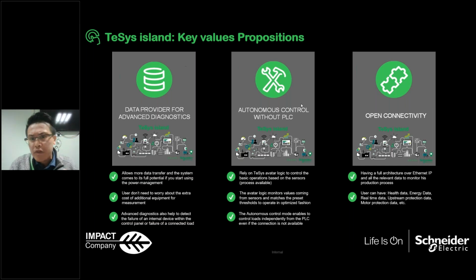basic application. But with the TeSys island, we can configure it inside the bus coupler. Because we have different sensor inputs to the system, you can set different parameters for the sensors. And when these parameters reach a certain level, you can start and stop the pump automatically. So without the PLC, for a typical small and medium-sized pump application or other applications, you can save the space and cost of the PLC. Because with the TeSys island, you can achieve this autonomous control without the PLC. We will talk about that more later. So you can save the cost of the PLC and also save the time of programming the PLC.